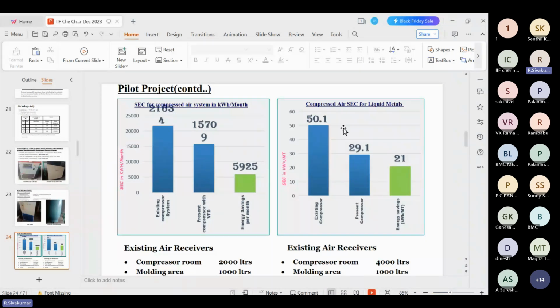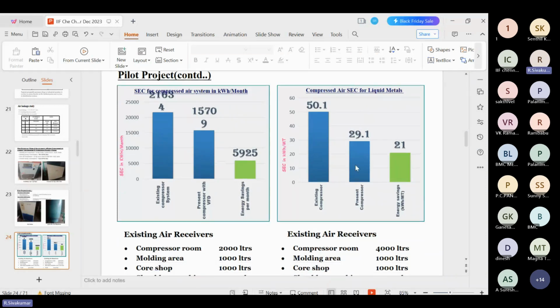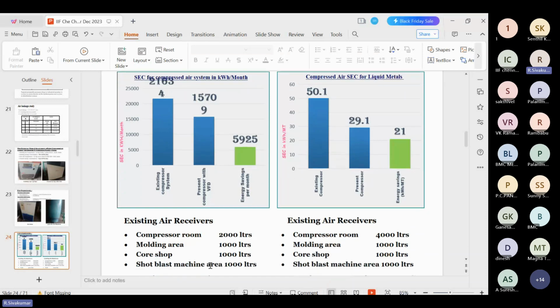If you compare the specific energy consumption for liquid metals, earlier it was 50.1 kWh per tonne of liquid metal. Now it is only 29. So 21 units were saved for every tonne of liquid metal produced. These are the other things. The existing receiver is 2,000. So totally 5 KL of receiver is there. Now it is 4,000 plus 1,000, so almost 7,000 liters of receivers were adopted.